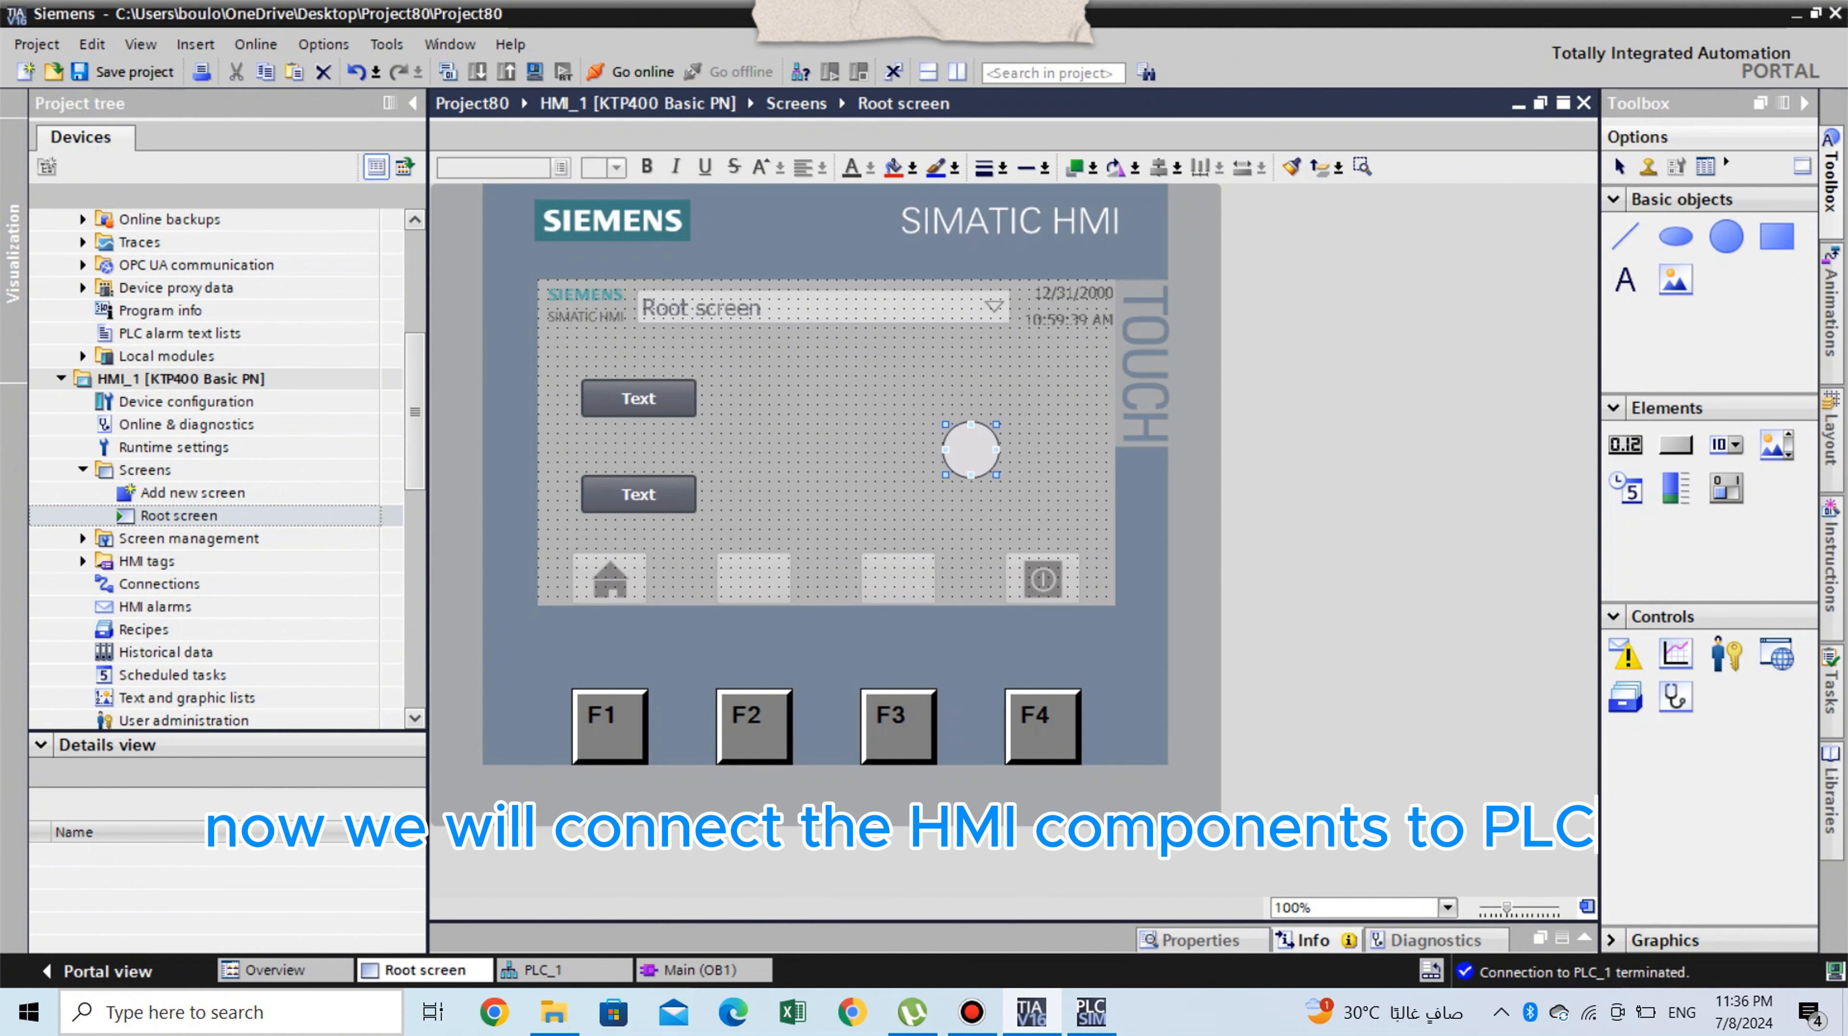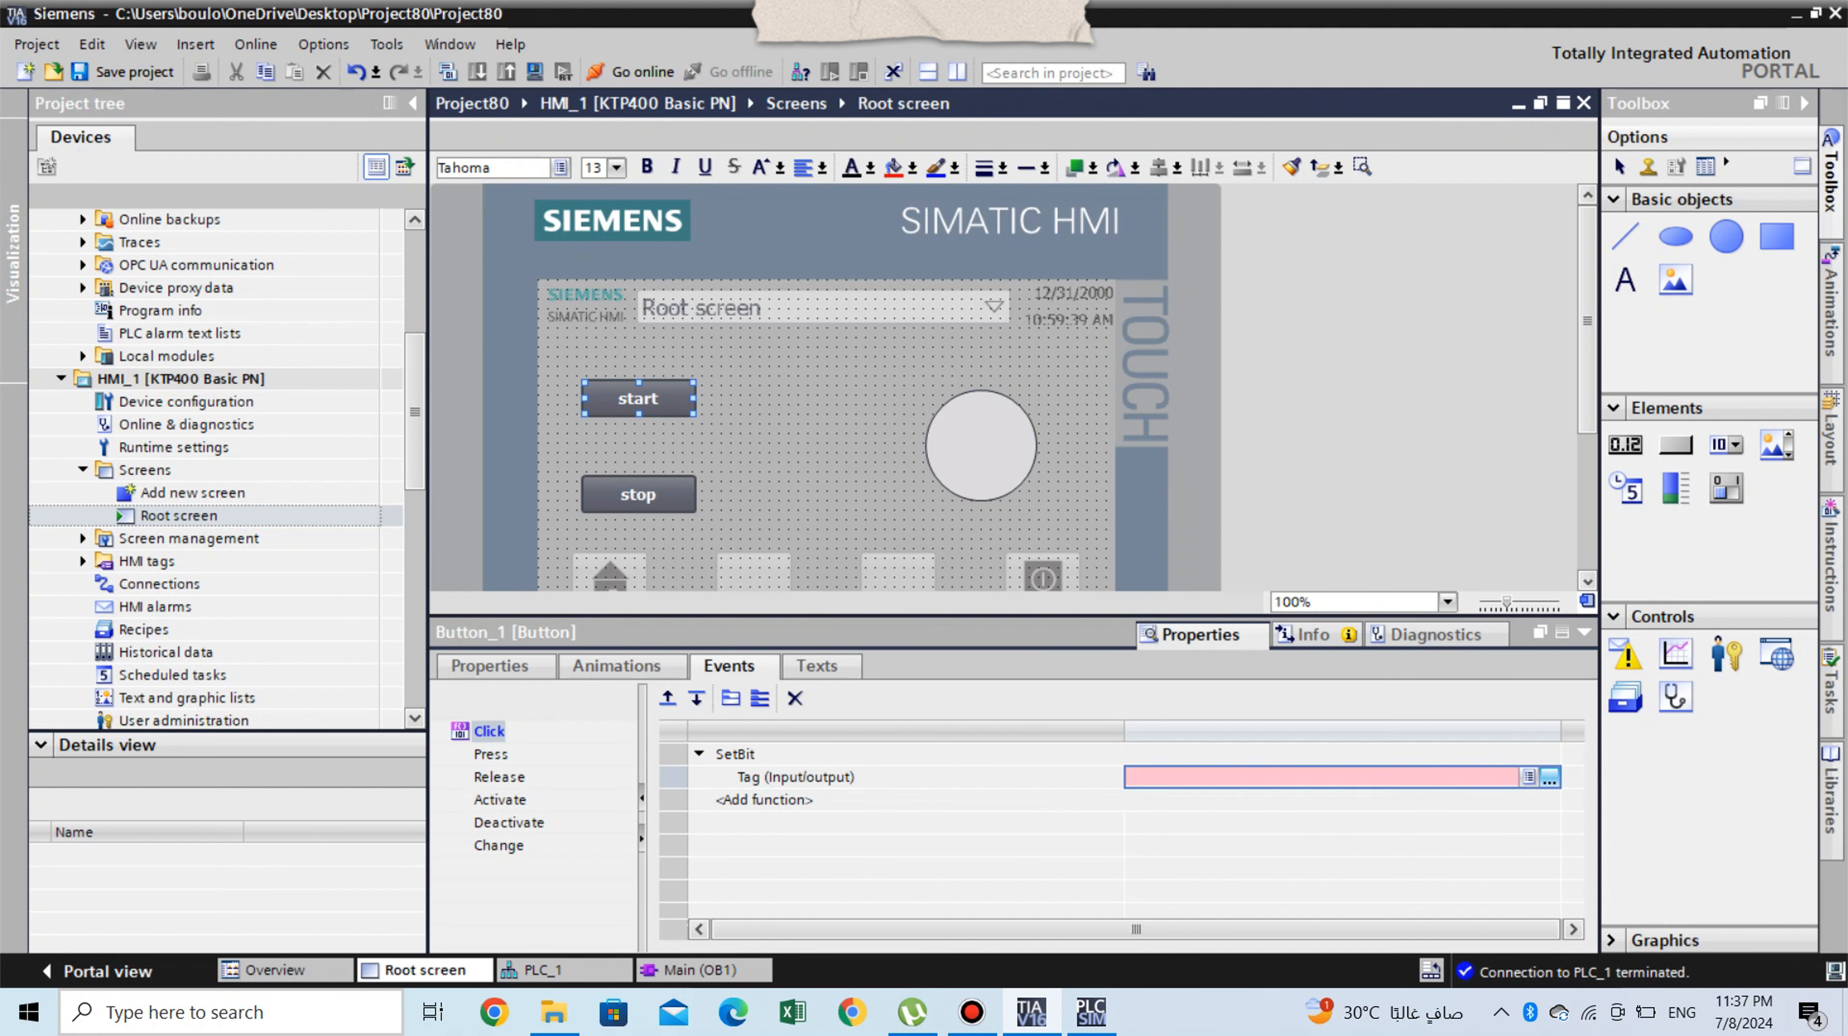Now we will connect the HMI components to PLC tags by following these steps. Select the component and choose properties. From properties choose animation. After that choose the action, in our case we choose press and choose what you need to happen when press the push button, after that connect it to suitable PLC tag as shown.